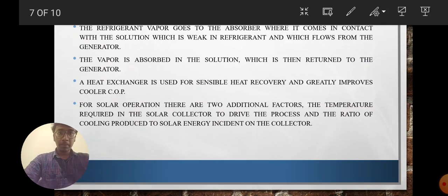The refrigerant vapor goes to the absorber, where it comes in contact with the solution, which is weak in refrigerant and which flows from the generator. The vapor is absorbed in the solution, which is then returned to the generator. The heat exchanger is used for sensible heat recovery and greatly improves the cooler COP. For solar operation, there are two additional factors: the temperature required in the solar collector to drive the process, and the ratio of cooling produced to solar energy incident on the collector. These are the two additional factors.